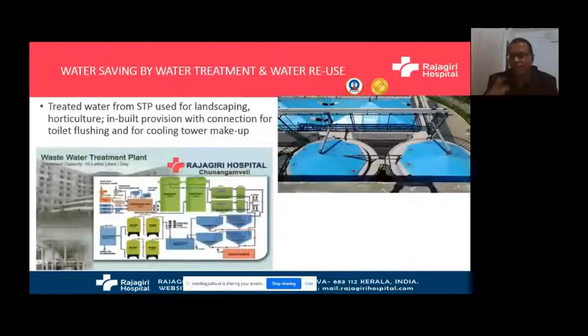Now, as we have huge water requirements for operation, where does all the wastewater go? 6 lakh liters will again come back as waste. Putting that into a main drain is normally done in many hospitals in many cities. But if you have your own sewage treatment plant, the 6 lakh liters can be treated. You can have ultrafiltration, bring down the BOD of the water to less than 3, and make it usable for toilet flushing.